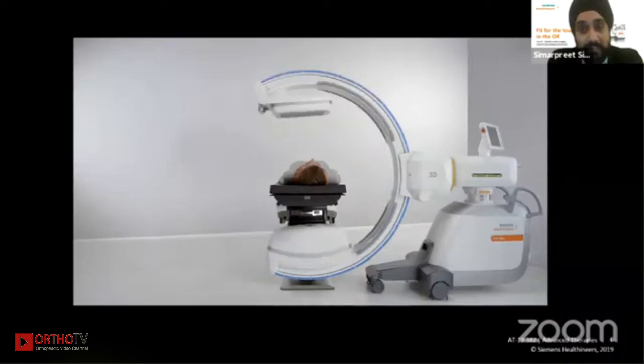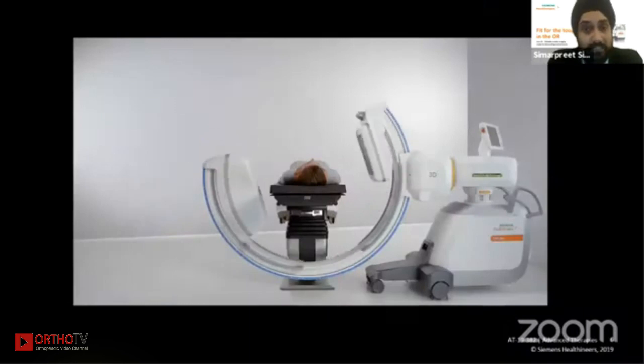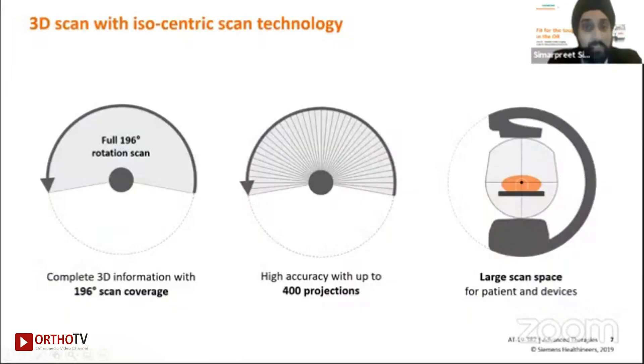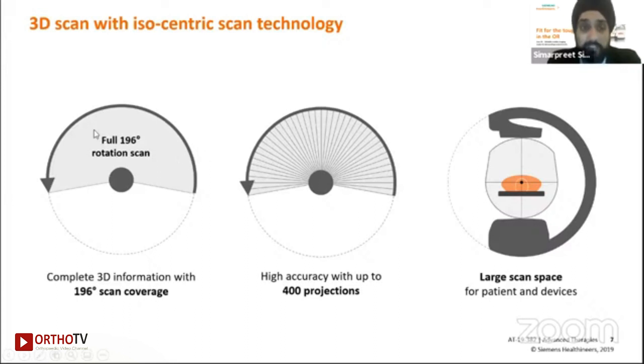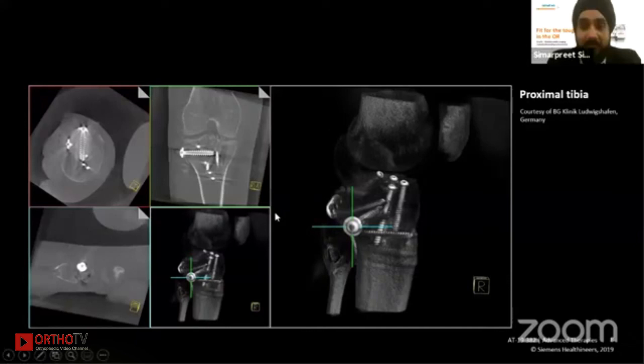This video shows how the 3D C-arm works and how it acquires CT-like images inside the OR. The C-arm acquires an image around the patient body and reconstructs it into a 360-degree volume. It works similarly to a cone beam CT, acquiring 196 degrees and then reconstructing a 360-degree volume from that acquired arc. The images are similar to what you would get on a CT scanner — you get all three planes: coronal, sagittal, and axial views, as well as a volume view.